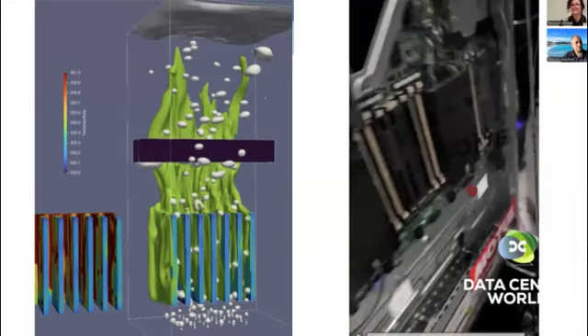So there are bubbles which are injected in this heatsink in immersion, and by this it allows increasing the temperature of the fluid by 10-15 degrees. So why is it important for me? I'm focusing on data center decarbonization and heat reuse. When we talk about heat reuse, the higher the temperature we have, the better opportunity we have to reuse it. If we have 30 degrees water, our areas of using that low grade heat are limited. But if we increase it to 60 or 55 degrees, the areas of our usage will be much wider. And our substitution of fossil fuels by data center heat reuse makes a significant impact on the whole economy of Europe and the sustainability of the whole world.